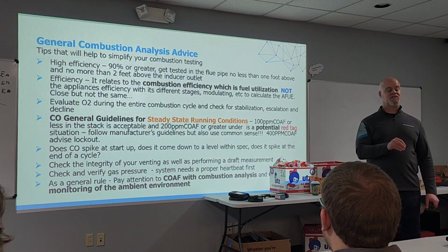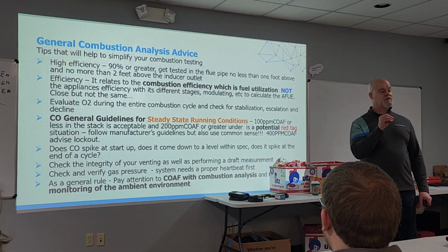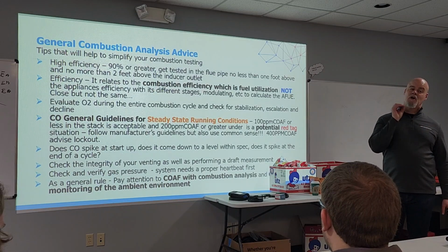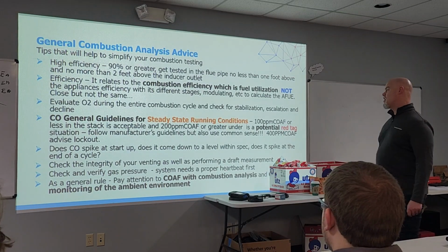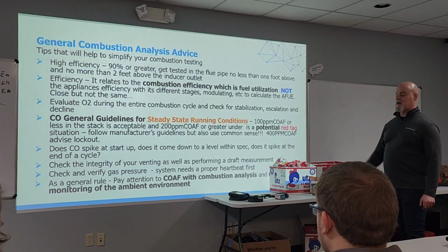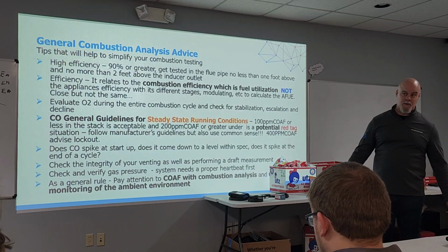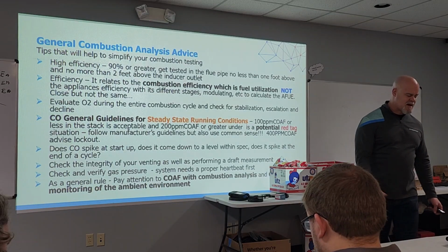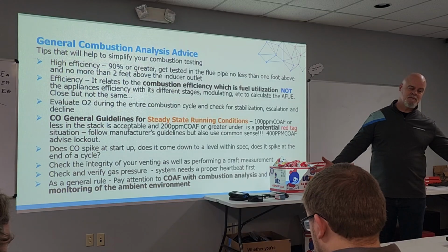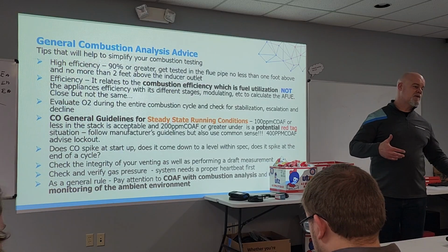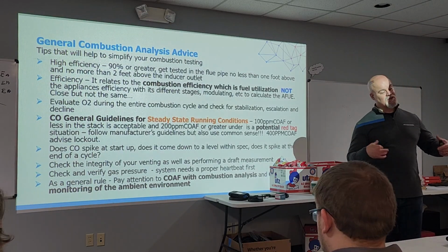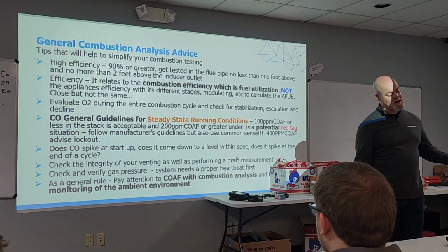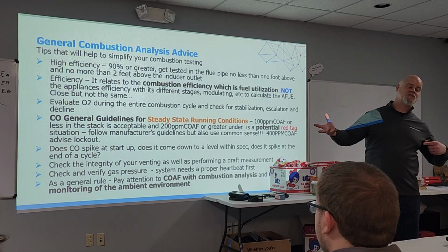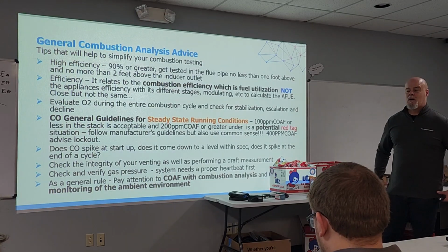The analogy is this. Your CO air free number is your hell number. If your hell number looks like heaven, you're in good shape. So we use CO air free for combustion testing. For example, if you had a CO number of say 17 ppm, your CO air free number could be anywhere from 37 to about 48 ppm. If you had a CO number of 100 ppm, CO air free could be as high as 200 ppm. So that is why we get granular.